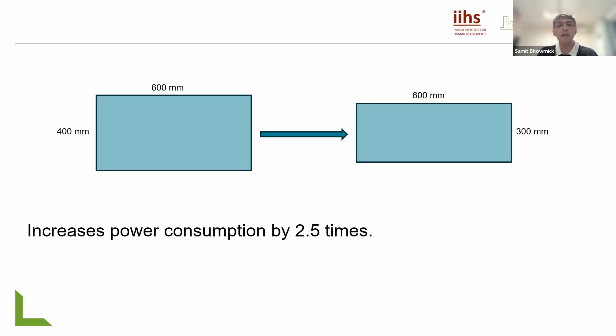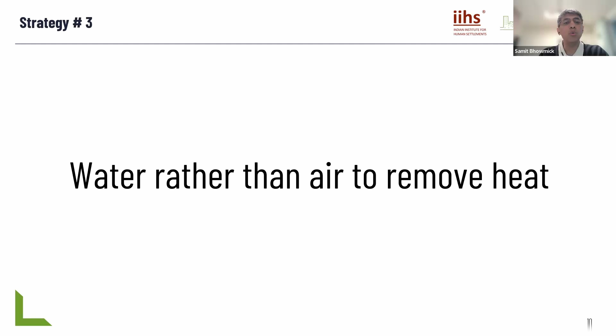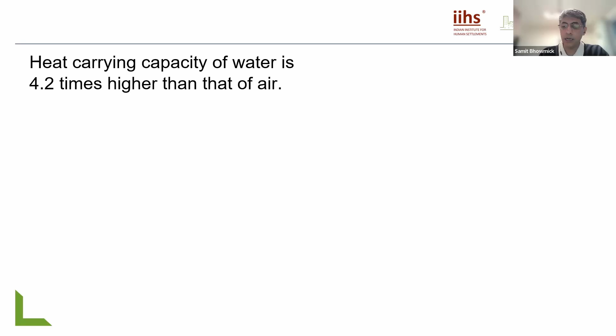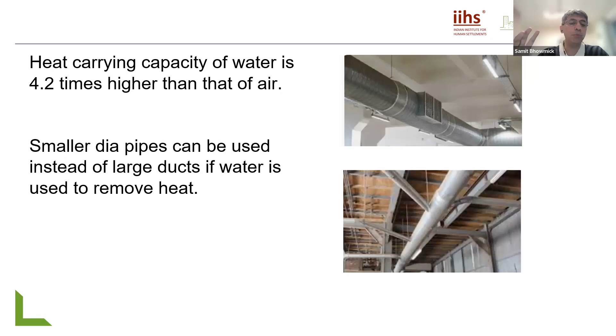This is another trend that has been used widely in other countries, and is now catching up in India as well. Water has a higher heat carrying capacity, about 4 times higher than air. Because it is so efficient, you can use small diameter pipes instead of large ducts to remove heat. This is of great use when we're talking about building floor-to-floor heights and higher false ceiling heights.